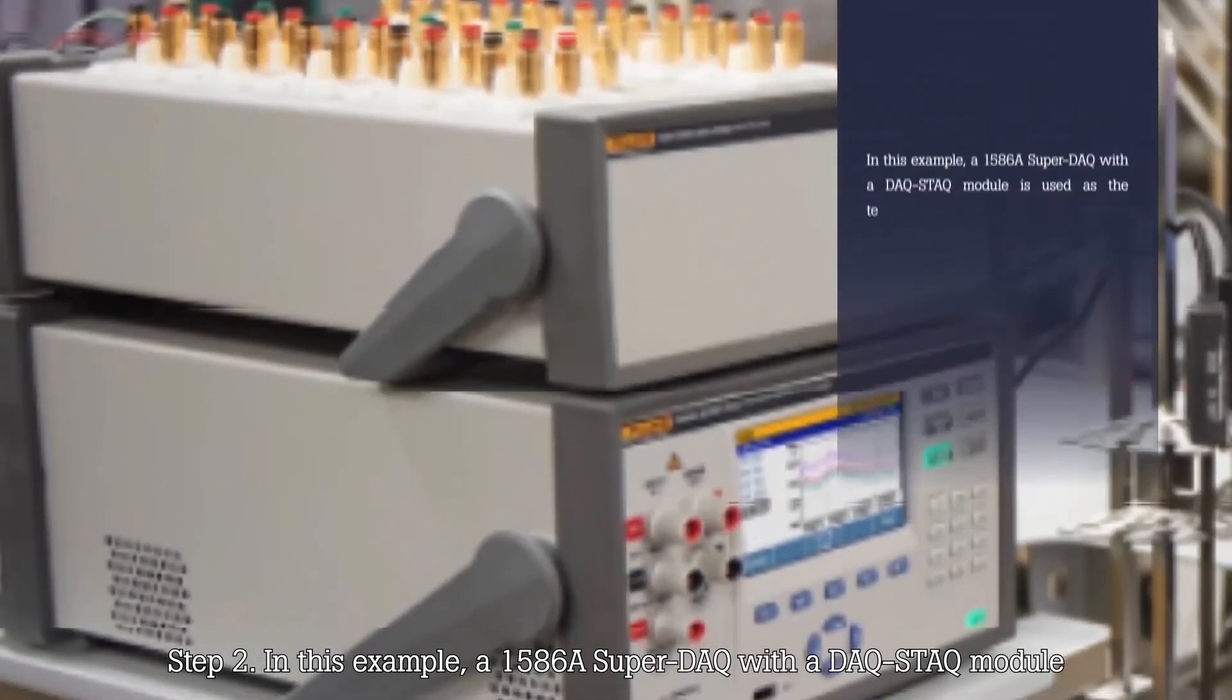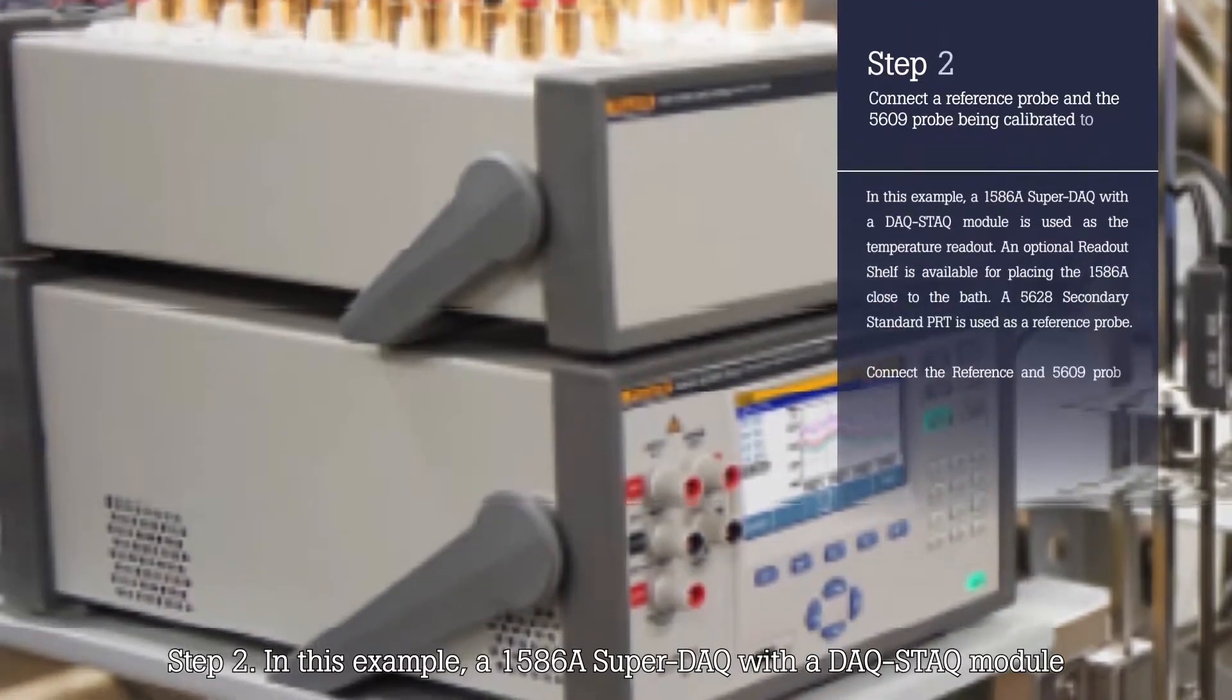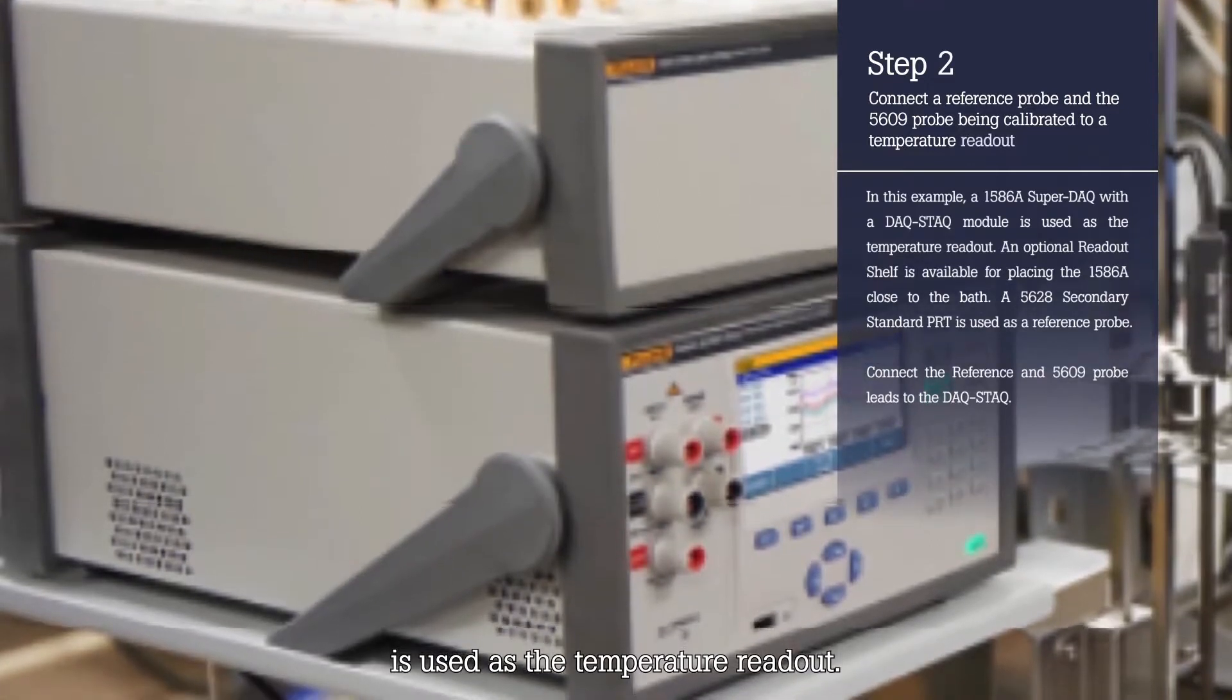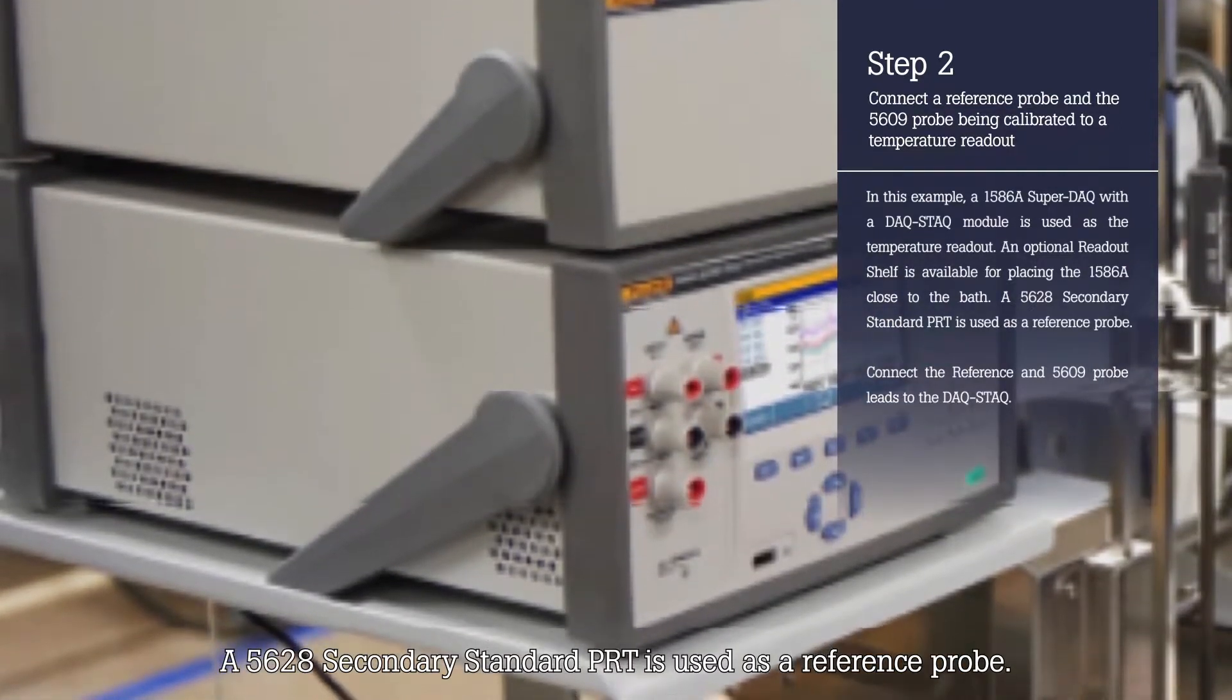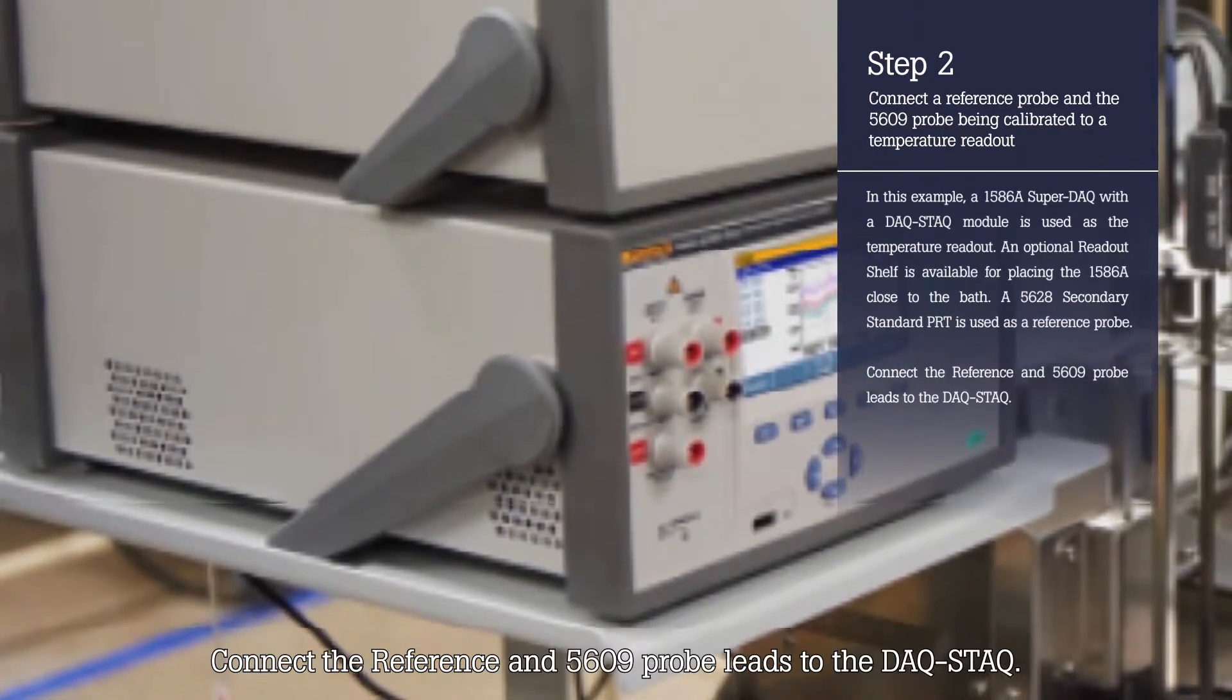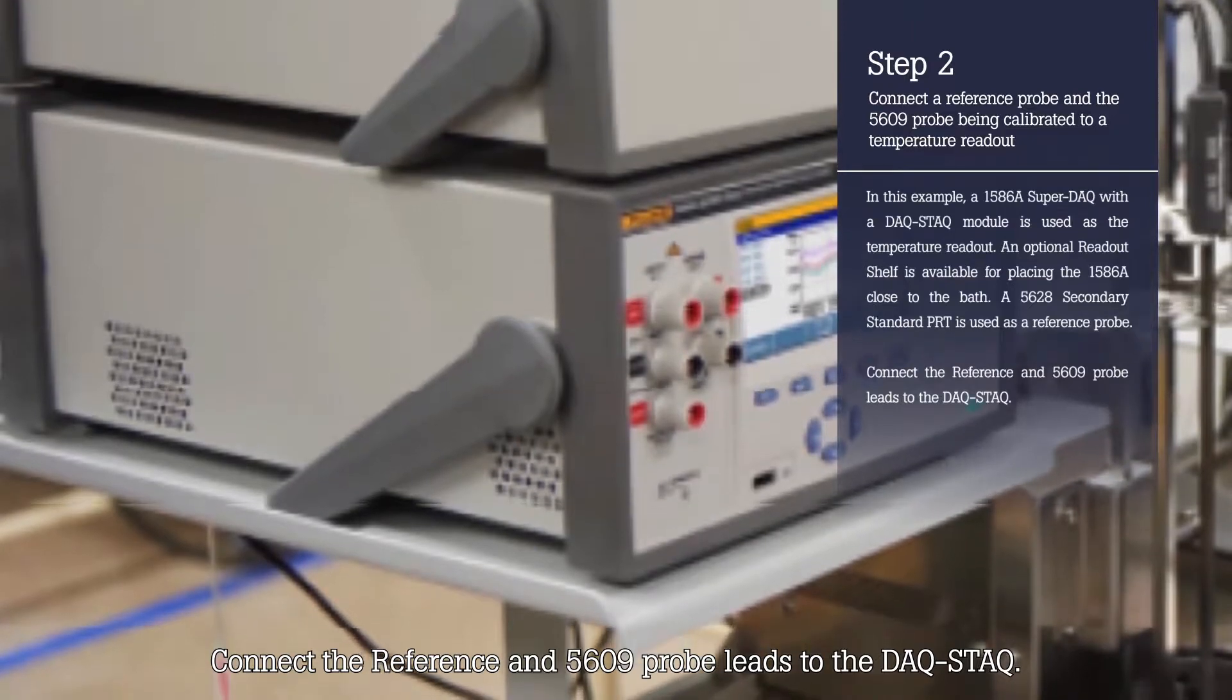Step 2. In this example, a 1586A Super-DAQ with a DAQ-STAQ module is used as the temperature readout. An optional readout shelf is available for placing the 1586 close to the bath. A 5628 secondary standard PRT is used as a reference probe. Connect the reference and 5609 probe leads to the DAQ-STAQ.